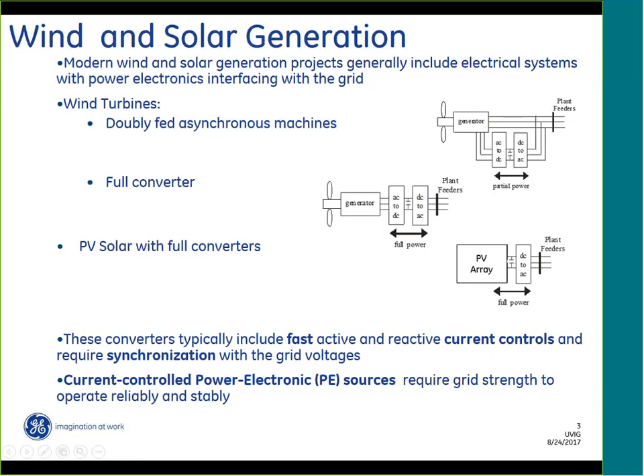Then there are also wind turbines with full converters. In that case, the generator has a converter for the full power—all the power from the generation passes through a converter before connecting to the AC network. Similarly for PV solar, a PV array is connected to a DC system that then connects to AC, with all the power from the PV array coming out of a converter. So these three concepts have different levels of power conversion.